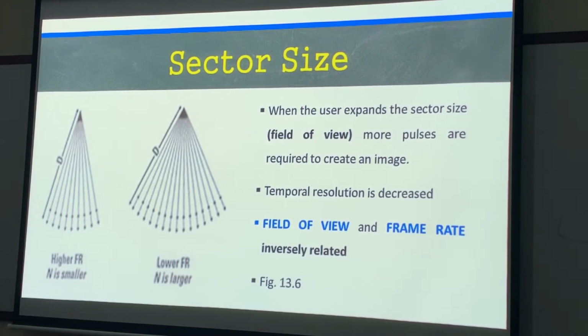And when we use the Doppler, that's something else. Now you're making it even longer to create that image because you're adding an application on top of a 2D image. Every time you add something, you're going to decrease the temporal resolution. You're going to decrease the frame rate because now it's taking longer to create that image. So when I add pulse wave Doppler, when I add color Doppler, now it's taking 3 times as long to create one image. So this is just for the time, but the quality of the picture is the same? The same.